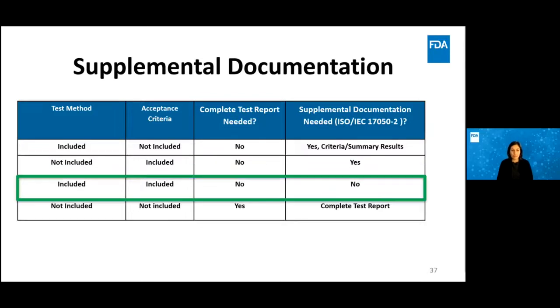As you can see in the green box, when both test methods and acceptance criteria are called out in the standard and the manufacturers use and apply them as written, FDA doesn't need any supplemental documentation. This is really the best case scenario, as it can save both the manufacturers and FDA time. One caveat is that sometimes standards offer choices in the test methods. And when that's the case, the manufacturer should let FDA know which method they chose and why with their supplemental documentation.